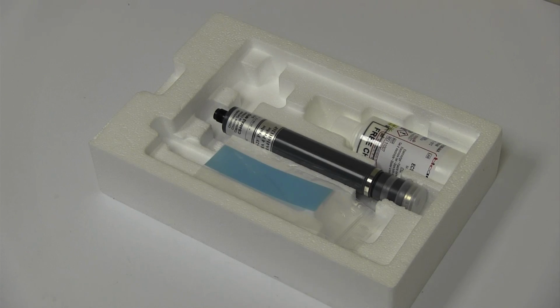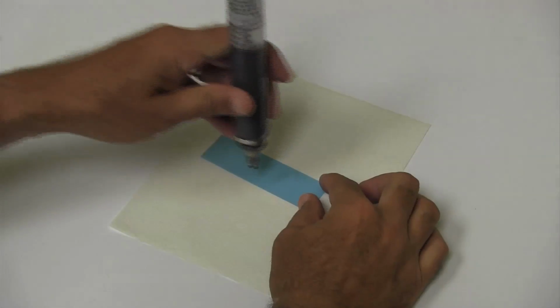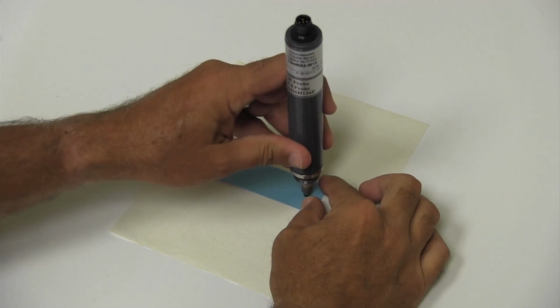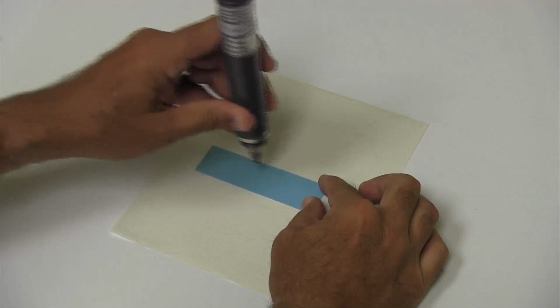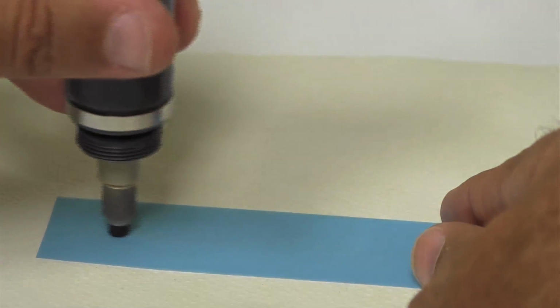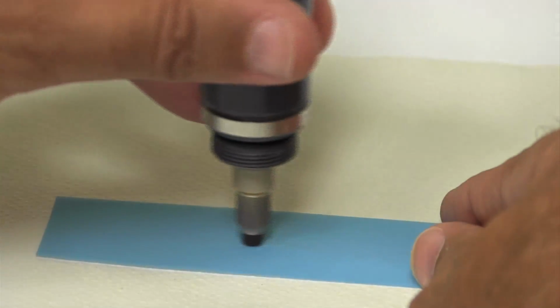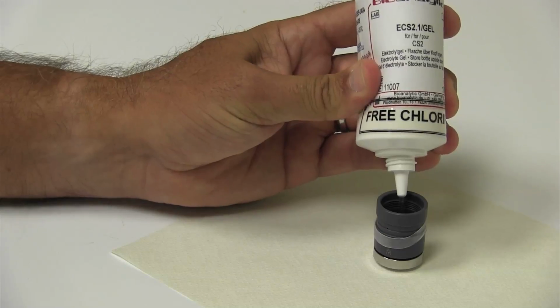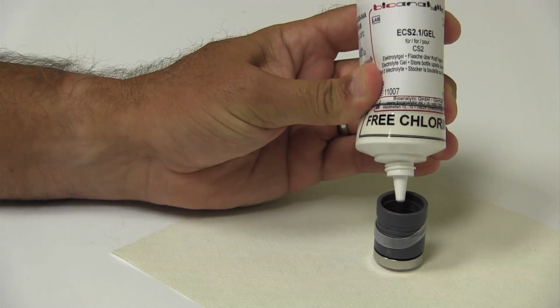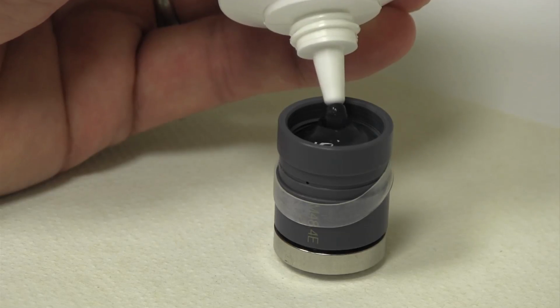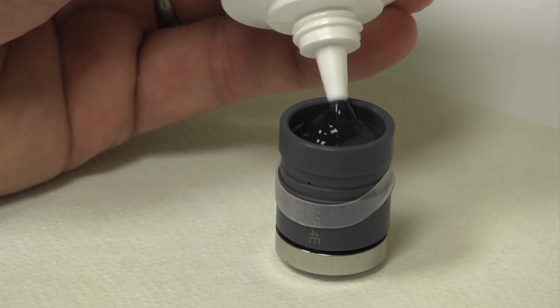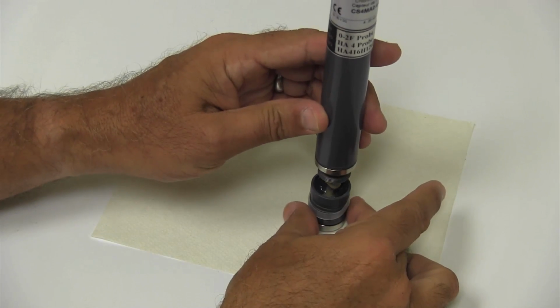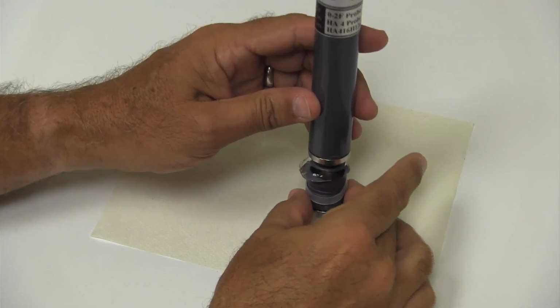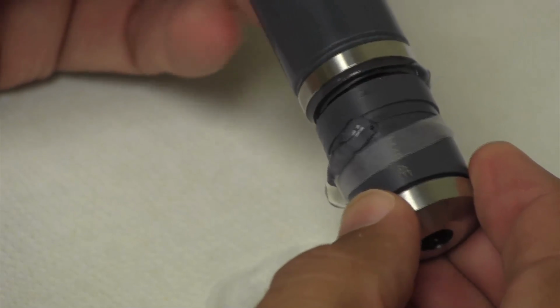The assembly process is quite simple. Clean the working electrode by placing the blue abrasive paper flat on a paper towel and run the tip across the paper 2 or 3 times to clean the gold surface. Slowly fill the membrane cap to the edge with electrolyte gel, not allowing any air bubbles to form. Hold the probe body upright while inserting it slowly into the membrane cap, and screw the cap onto the probe.